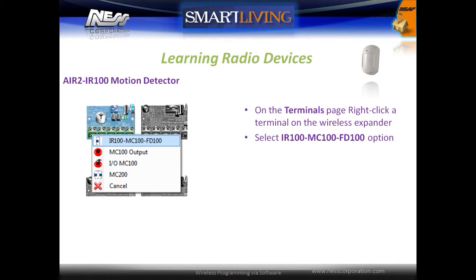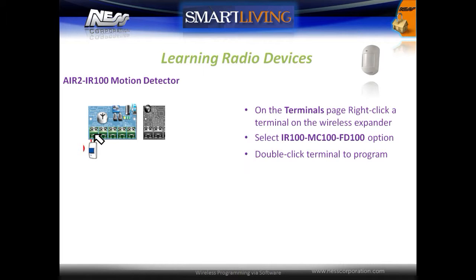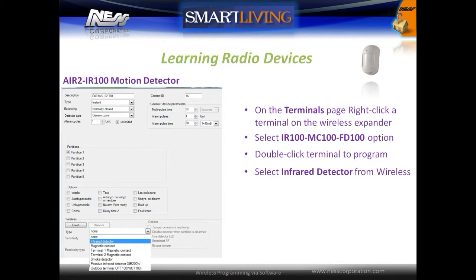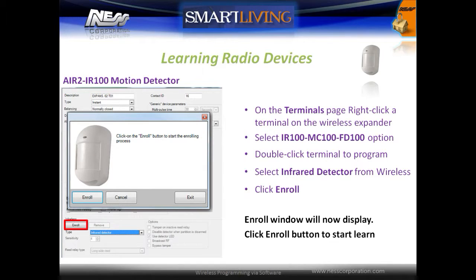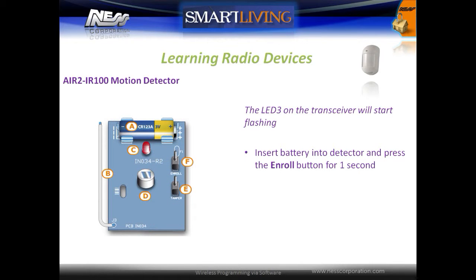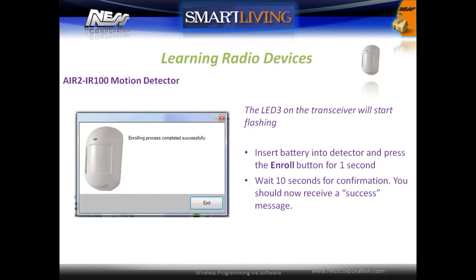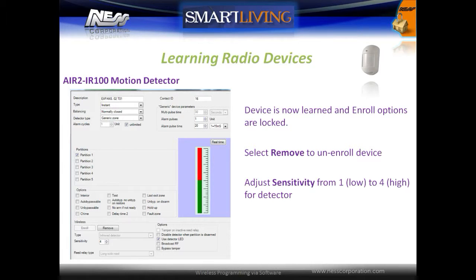On the terminals page, right click on a terminal on the wireless expander to enroll the sensor into, and select the IR100 option. Double click the terminal to open the programming window. Under the wireless programming section, select the type as infrared detector. Click the enroll button to enroll the detector. Once the system is in enroll mode, the transceiver's LED 3 will start to flash — press the enroll button on the device. After about 10 seconds, a message should confirm that the device was enrolled successfully. The device is now learnt and the enroll options are locked. Adjust the sensitivity of the detector if required, between 1 and 4.